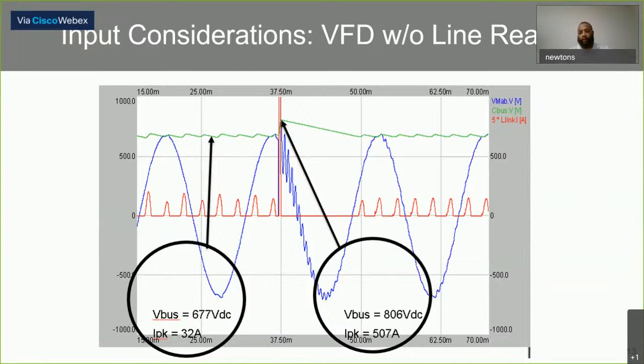So if you have a 40 amp drive, it's not designed to be taking in 507 amps, along with the cables that are feeding that drive as well. So those are some issues that you need to design for. So how can we fix that?